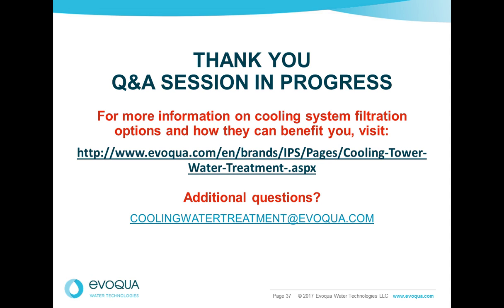Just be careful. Obviously, again, work with a chemical company. Don't do that on your own. You could spring a bunch of leaks. Exactly. Sometimes that rust is just barely holding the metal together, and you'll end up breaking free a lot of leaks, and your heat exchanger will turn into Swiss cheese pretty quickly. So again, I can't emphasize enough: work with a good water treater.